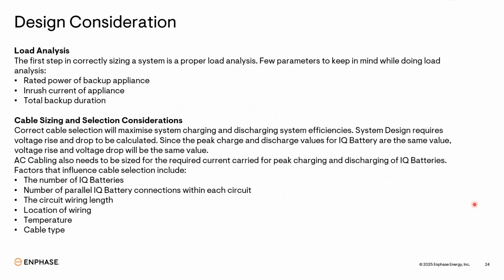This is totally AC. There is no DC cable inside this system, so the calculation will be easy. Like you do for your normal plant AC calculation, the same calculation will apply here. You need to make sure of this once you are calculating the cable sizing. If the home is a three-phase wire system, earlier the load was divided over three phases, and now you are doing the backup in single phase only, and you are increasing the loads on a single phase. The outgoing cable from the main side, earlier it was a 6 square cable, and now you are transferring all loads to a single phase for backup purposes.